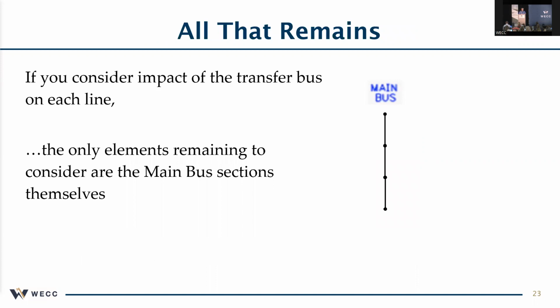If you do all that, if you go and get all this information, and the auditors, even though they're just sampling, pick a sample and include all the breakers, then the only thing that's left out of the sampling process, as far as auditors having reasonable assurance, is, well, we didn't ask about the main bus. But this is true for all other bus configurations also: for main buses there's a very low risk that your facility is limited by the main bus inside a switch yard. So we're covering most of the risky bases. We're focusing on the risk elements by including the breakers, the drops equipment, the terminal equipment for the breakers and everything in there, even if it goes out to 2 breakers.